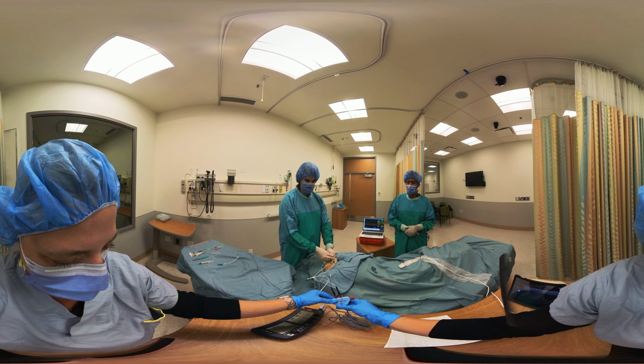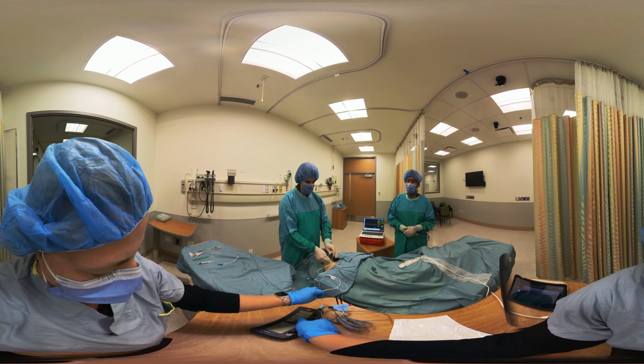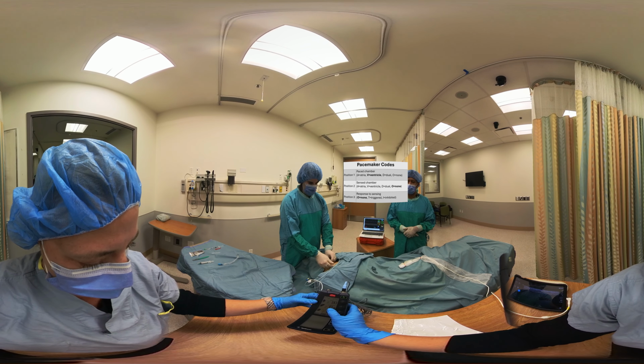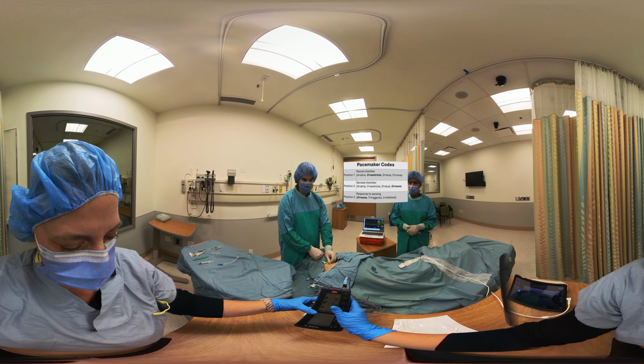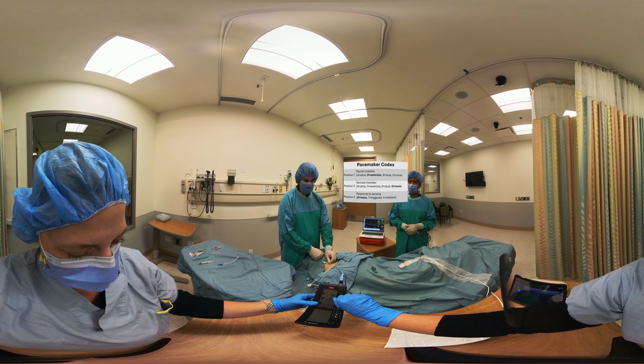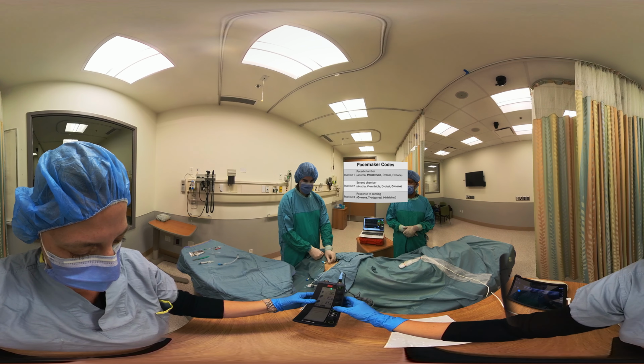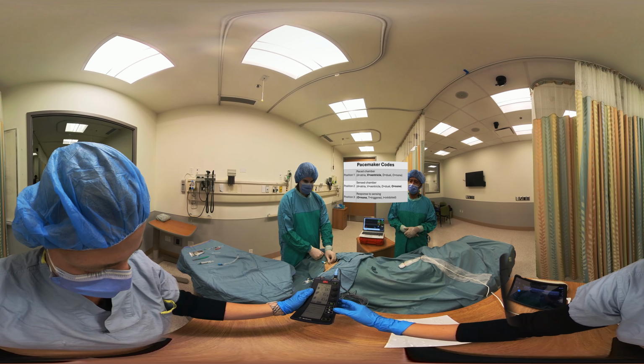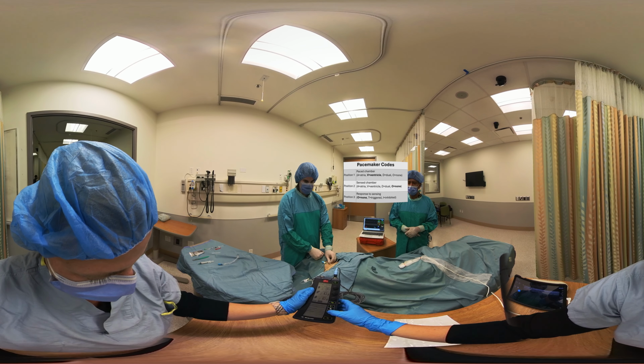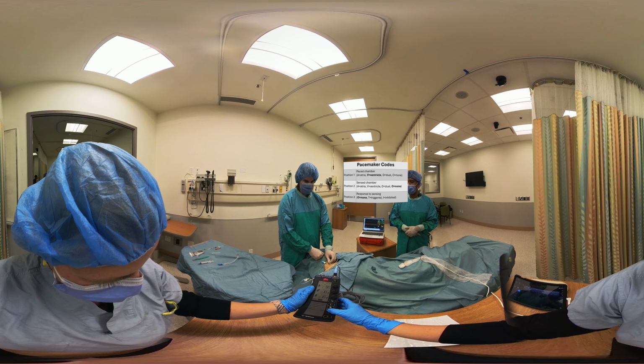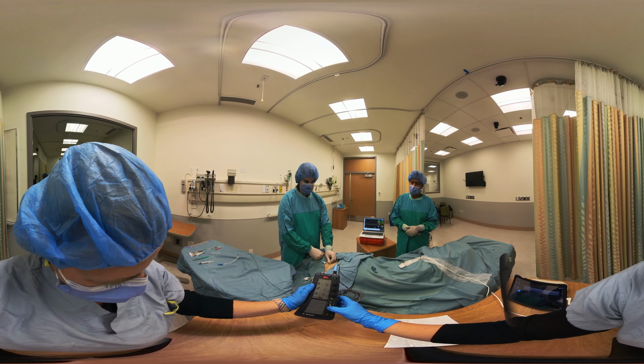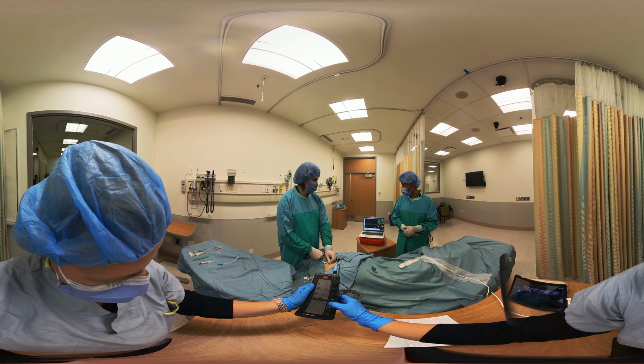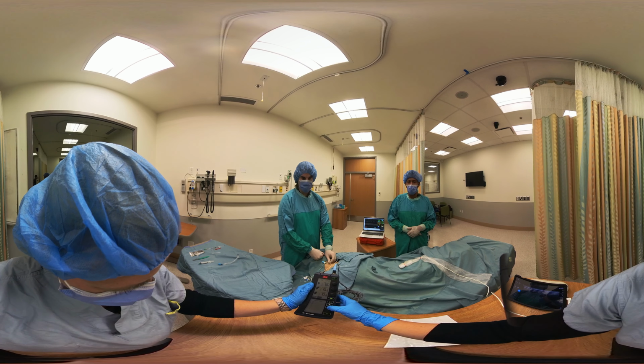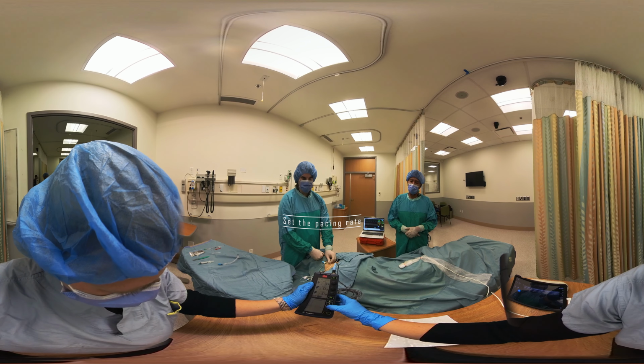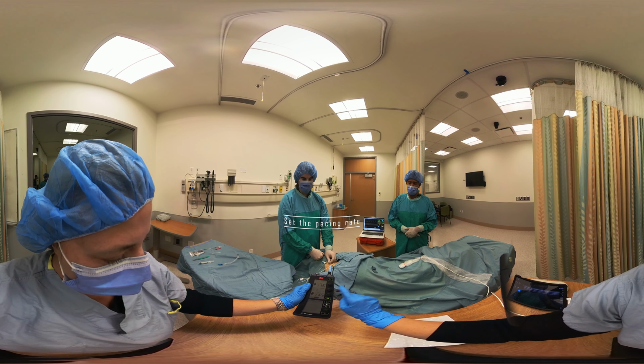Usually, the primary operator will tell you a setting to use. Most of the time, this will be in a VOO mode. What this means is that we are pacing the ventricle. We are not sensing the ventricle, in other words, the first O. And the third letter means that we're not doing anything if we sense something. In other words, this is fixed pacing. You typically will want to choose a rate that is faster than the patient's intrinsic rate. In this case, because this patient is in third degree heart block at approximately 30 beats per minute, we will use maybe a pacing rate of 80 beats per minute.